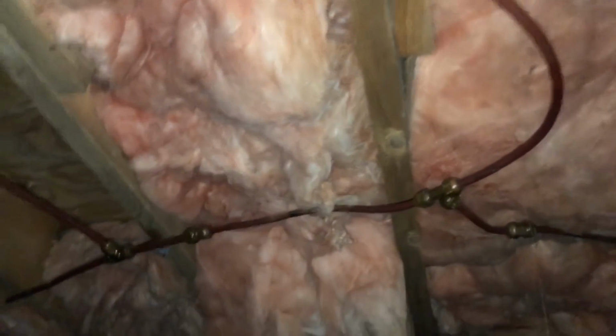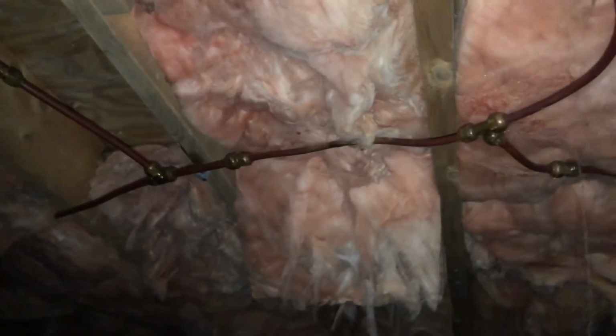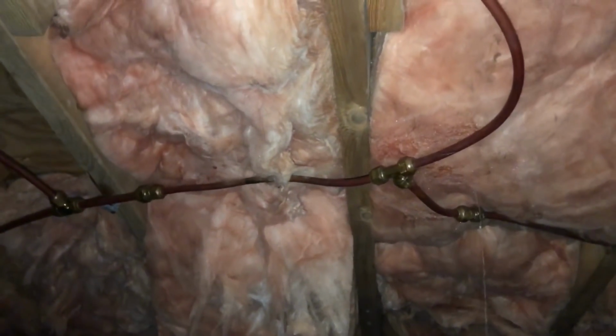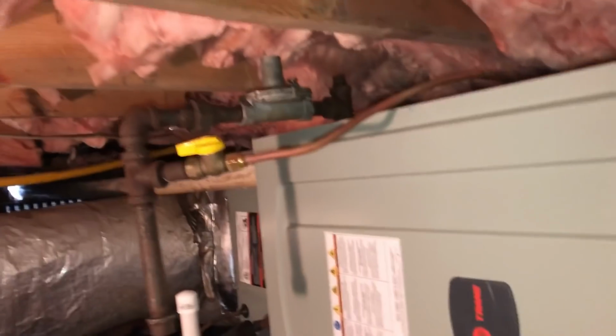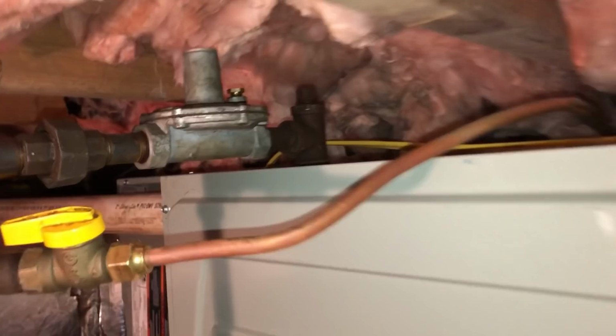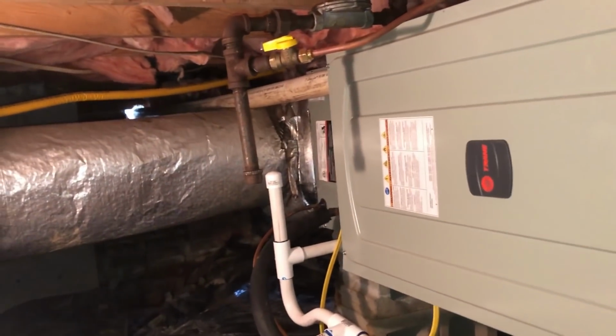But anyway, none of it's leaking, but I'm going to propose to this lady that we tear all of this out and start over and come back in here with CSST and run this out correctly and get all these fittings out of here. Let's put our insulation back up and we'll get out of here. I need to grab a few rods. But we got our station looking better. It's a little bit of a compact one, but it's right.